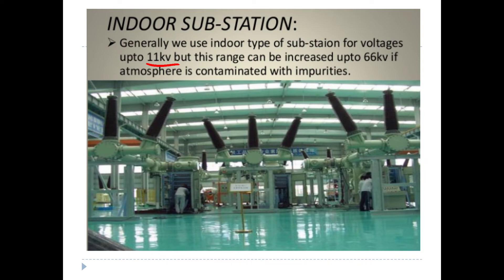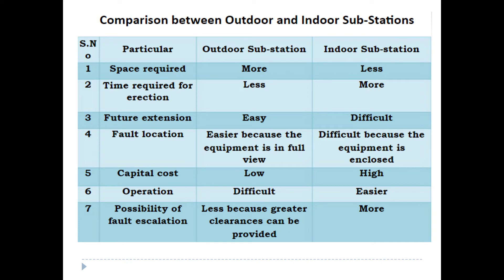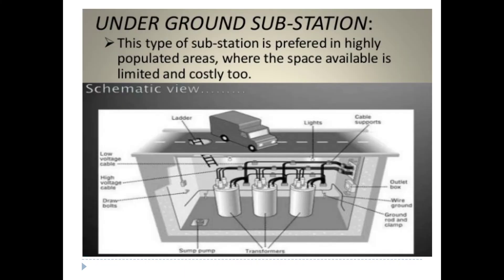If we go to the indoor substation, the atmosphere may be contaminated with impurities. Comparing outdoor and indoor: outdoor means less cost and less time required for erection, while indoor means more time required for erection. For future extension or adding equipment, it is very easy outdoors. Outdoor substations are easier for fault location and viewing equipment, while indoor is more suitable for contaminated or congested areas.